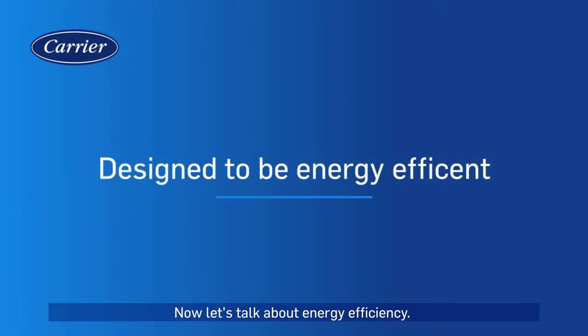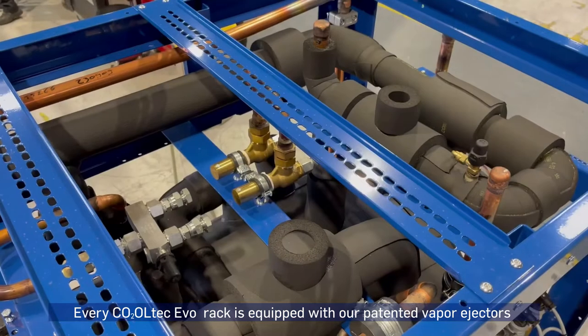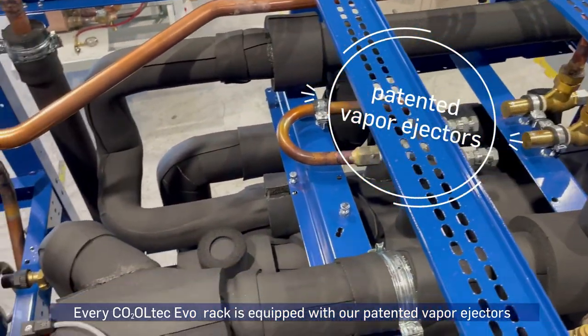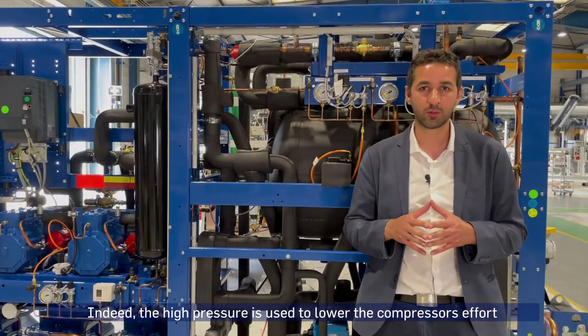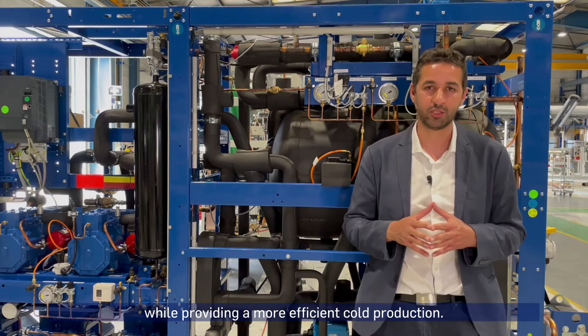Now let's talk about energy efficiency. How do we optimize energy consumption and reuse the heat produced? Every CO2OLtec Evo rack is equipped with our patented vapor ejectors, which reduce energy consumption by up to 30%. The high pressure is used to lower the compressor effort and electrical consumption, while providing a more efficient cold production.